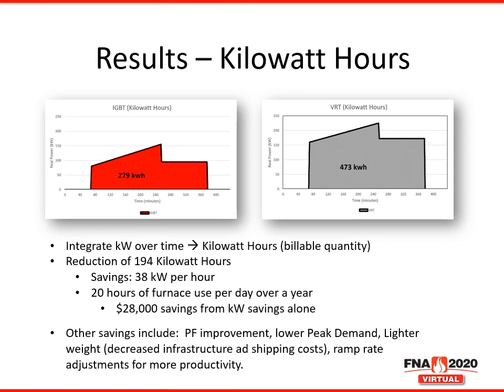If the furnace was used for 20 hours a day over the course of a year, the IGBT MFDC power supply could provide savings of up to $28,000 from kilowatt savings alone. This doesn't even take into account some of the other factors that could improve savings, such as power factor improvement, lower peak demand, and increased productivity from ramp rate adjustments.